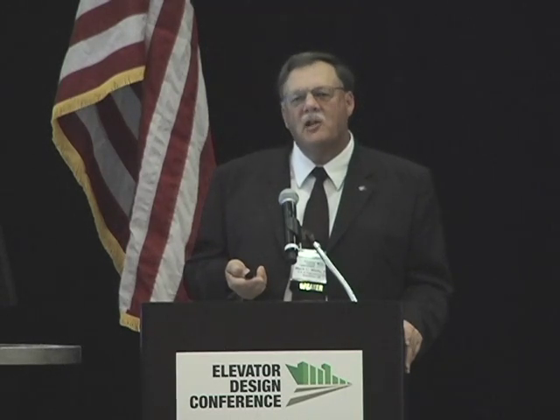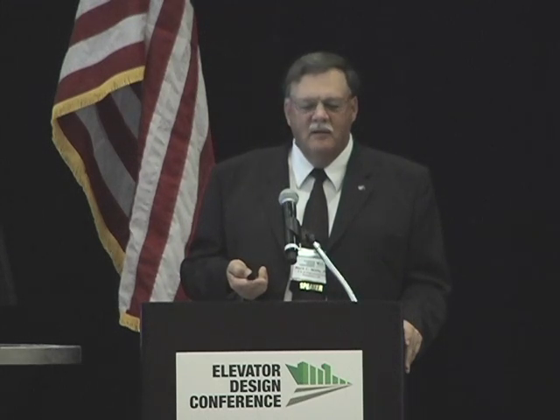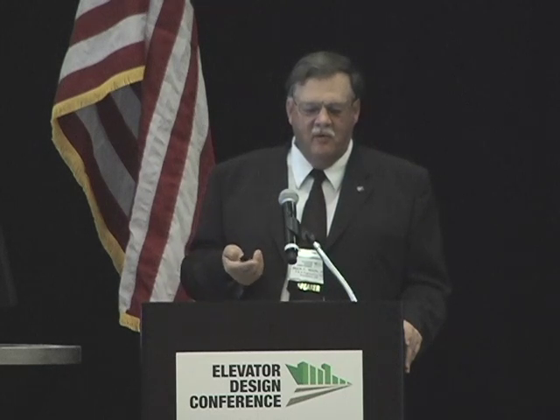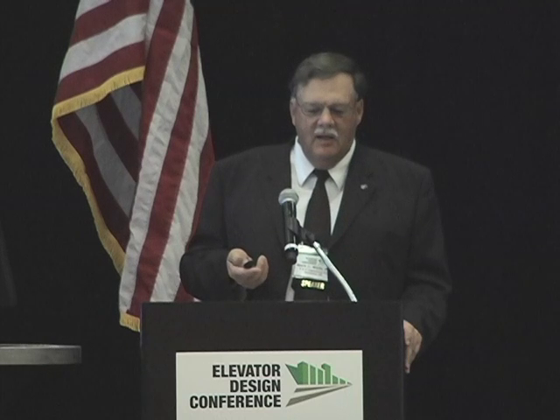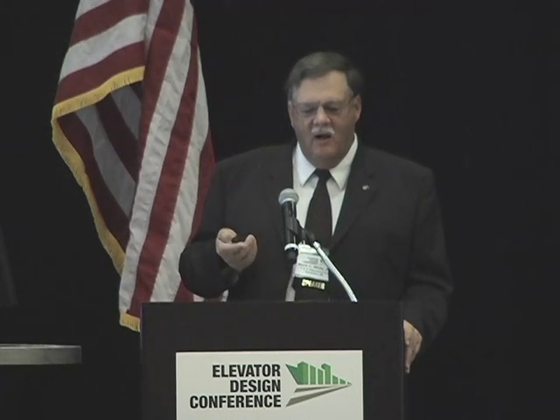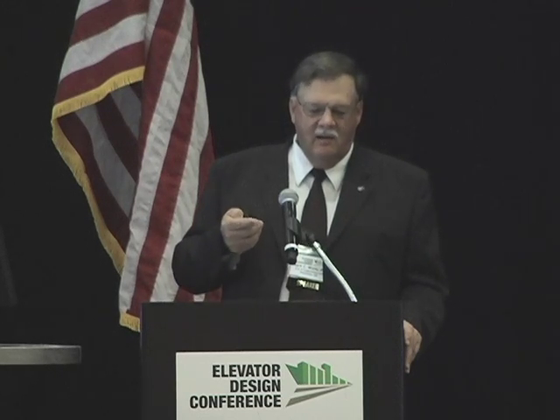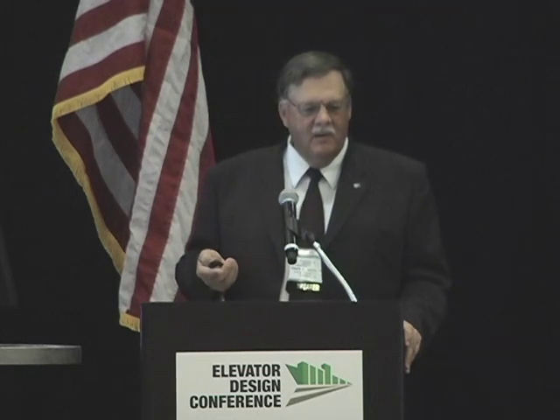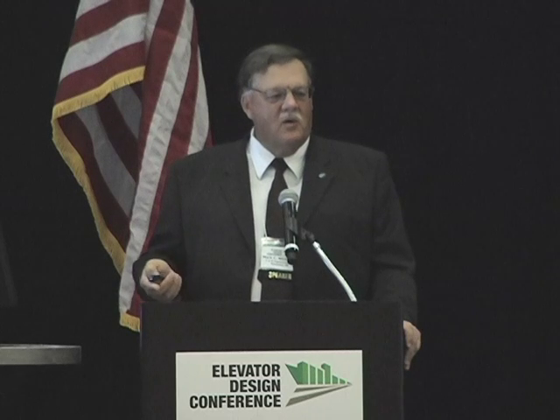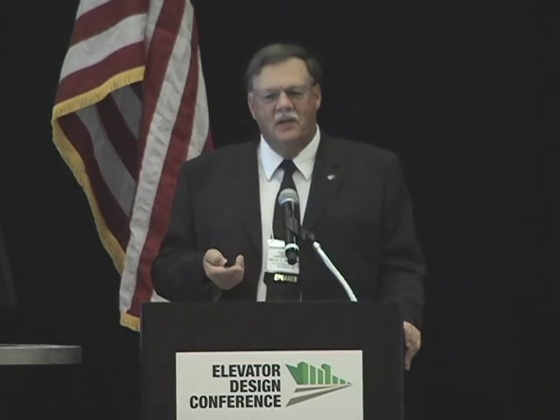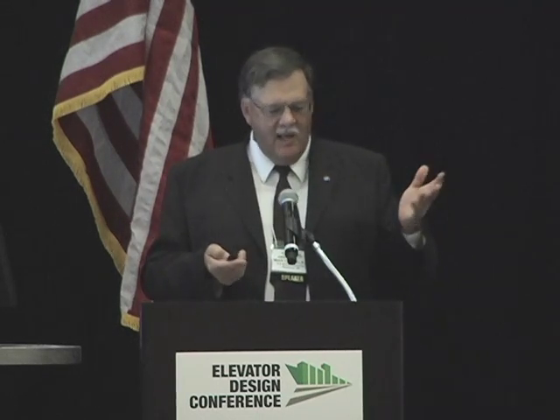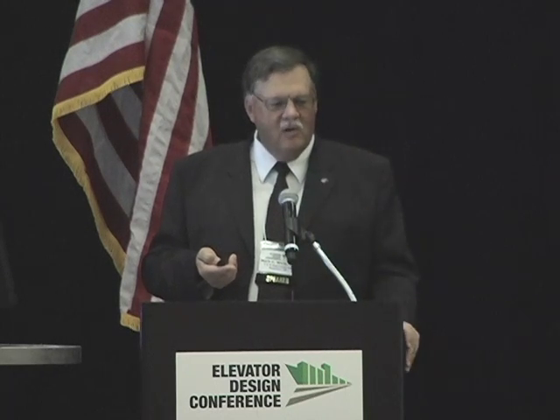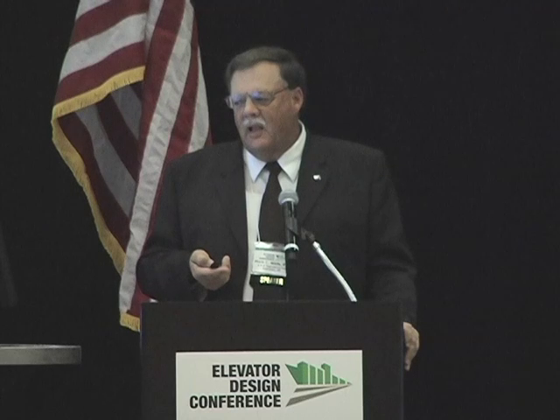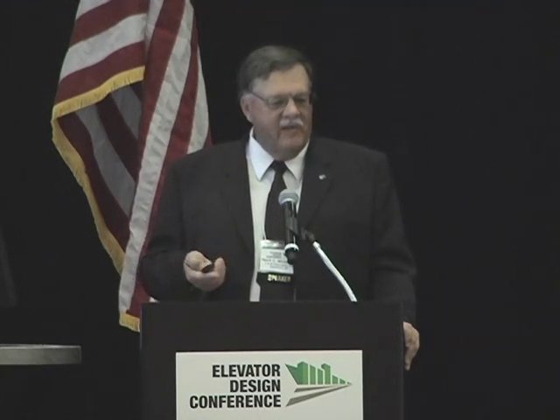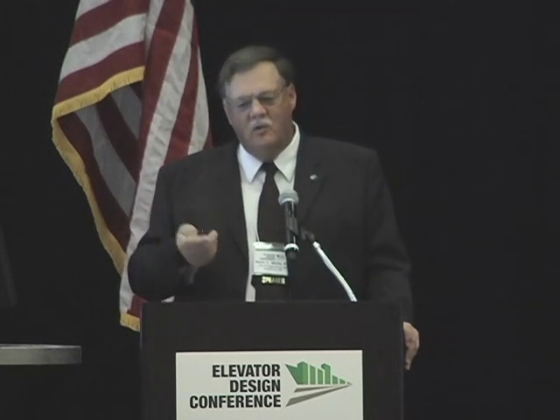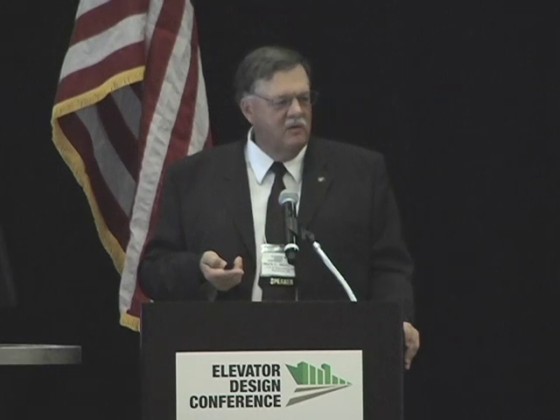The interesting thing about all these codes and standards is that NFPA 70 is a construction standard. In our committee, that I'm on the code panel for the electrical code, we have 500, 502, 504. We set the methodology for how materials are classified and what the requirements are for electrical wiring. But then other committees set what the criteria is for the materials. And so it's kind of like we said, well, we're going to make dust class 2. We're going to say it's agricultural dust, and well, there's coal dust and some other things too. But then we determine the classification for the purposes of electrical classification, and other standard groups set the standards for what those materials are and which ones are combustible and so forth and so on.